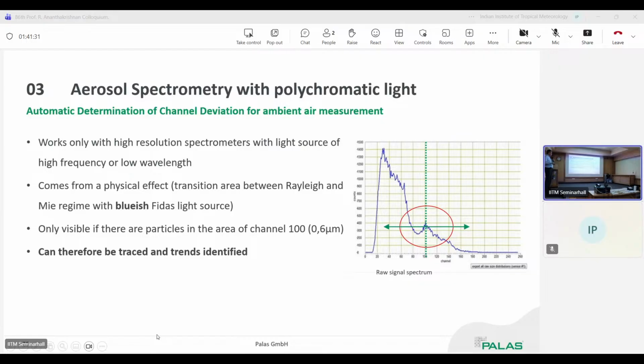And we monitor that point, and our system shows the channel deviation, meaning it shows what the drift actually is over a longer time. This, of course, always depends on the aerosol. If you have a very clean area, clean air, and not lots of particles in this area, at 0.6 micrometers, then you will most likely not see this, and the system will not see it either. But if you have clean air, the PM values are mostly very low and also not critical. If there is a significant number of particles in that area, then we can see it, track it, and alarm.